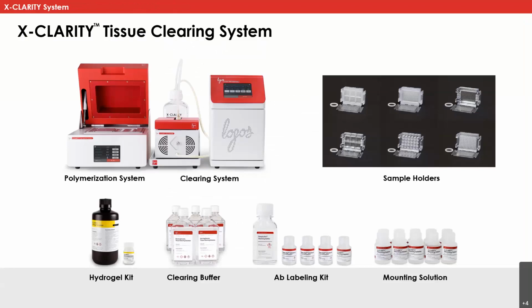Now, this is the X-CLARITY system itself, and it is composed of several different components. The main clearing system is what I'm circling with the cursor right now. Over here is the control tower, and the control tower controls the current, the temperature, and the pump speed. In the back, which may not be so visible because it's clear, is where we hold the SDS buffer. And then hopefully you can see these tubes that run from the control tower through the sample chamber right here.